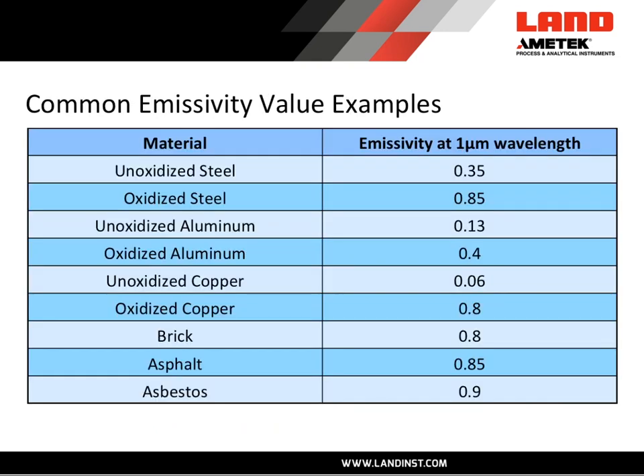In this slide we see emissivity value examples for common materials. Unoxidized steel — think of that as liquid steel — has an emissivity of 0.35. Whereas if it is oxidized and rough and dark, it has a higher emissivity of 0.85, emitting 85% of its energy. If we look at aluminum, unoxidized aluminum has a very low emissivity around 0.13, and fully oxidized aluminum has a higher but still not very high emissivity of 0.4.